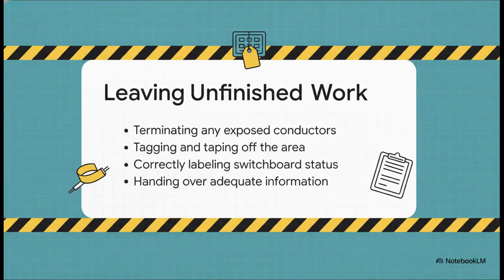But hey, what if you aren't done? If you're leaving unfinished work, you have to do it professionally so you don't leave a deadly booby trap for the morning shift, or worse, an unsuspecting civilian. The site has to be left in a perfectly safe state. That means terminating and fully enclosing any exposed wires. You must tag and physically tape off the electrical equipment and the whole surrounding area. Ensure the status of the switchboard is clearly labeled. And critically, you have to hand over adequate information to the workers who will be taking over so they know exactly what they are walking into.